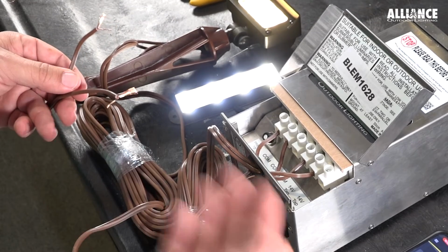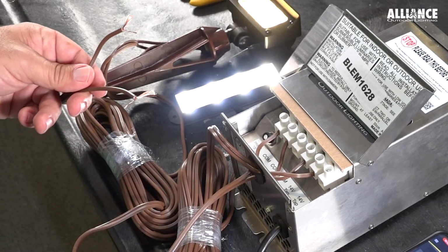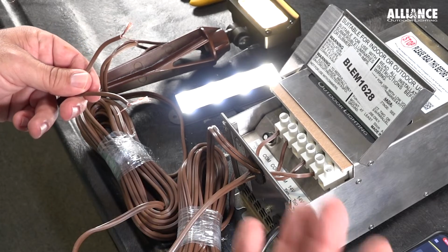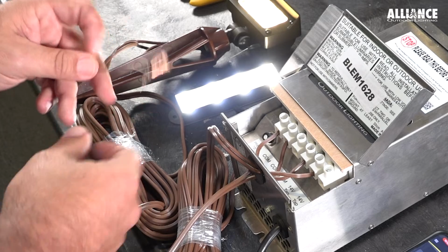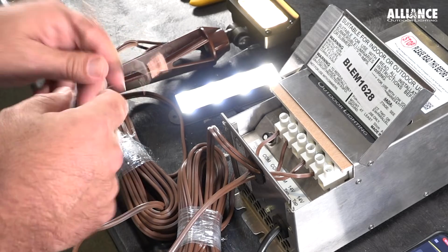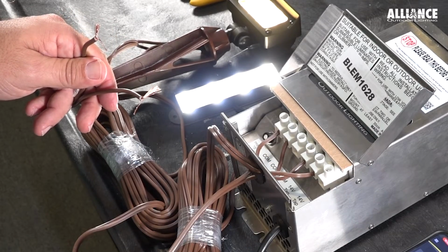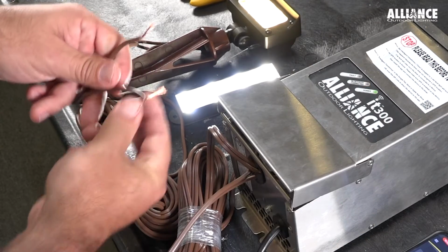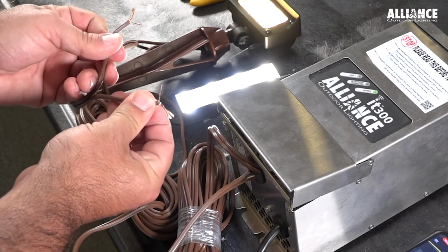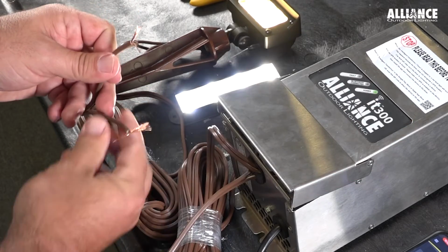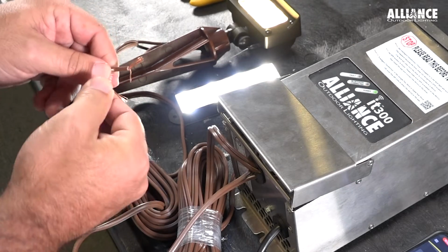Wiring issues are the most common reason to have a direct short in the field. That could be a fixture that's not only miswired, but a small amount of copper out of whatever wire connector you're using, touching, will cause this transformer to fault. I'm going to demonstrate that now by just touching these two wires together, and you'll see this transformer fault light come on and this transformer will turn off.